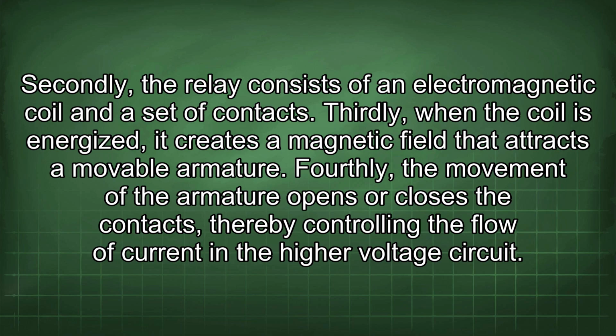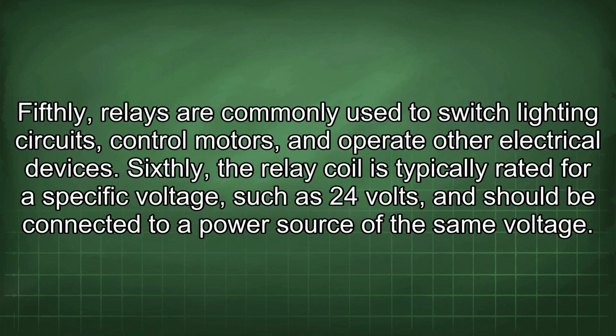Fourthly, the movement of the armature opens or closes the contacts, thereby controlling the flow of current in the higher voltage circuit. Fifthly, relays are commonly used to switch lighting circuits, control motors, and operate other electrical devices. Sixthly, the relay coil is typically rated for a specific voltage, such as 24 volts, and should be connected to a power source of the same voltage.